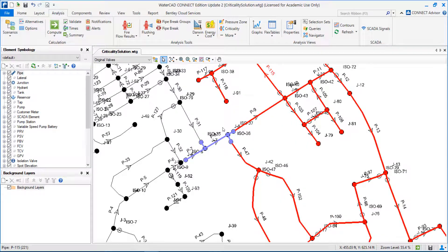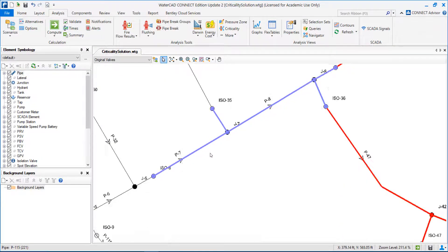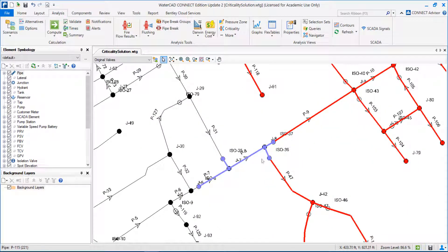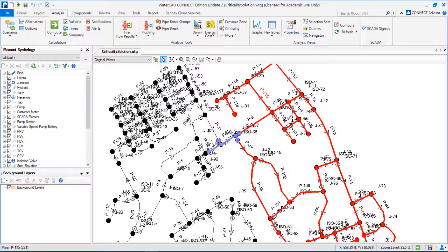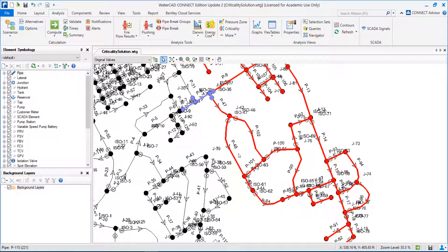A solution here would be to understand if we can place more isolation valves — for example, imagine placing an isolation valve before node J7. If I had a problem in this pipe, I would just need to close this pipe and water will move this way to supply all these areas. So if the burst was here and I had a valve here, this network would not be affected. But if I have a problem elsewhere, even with better-located valves, I'm not able to avoid interruption into this area.